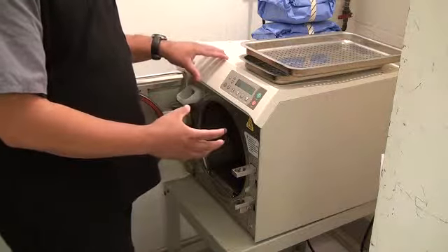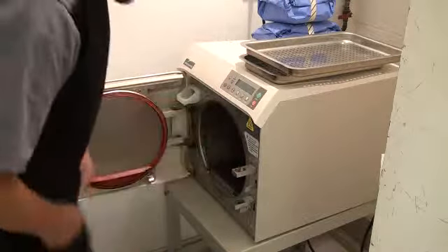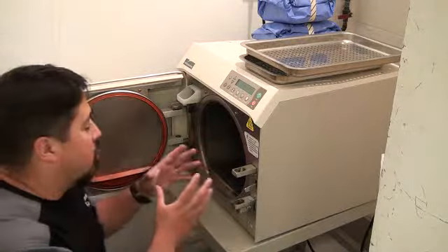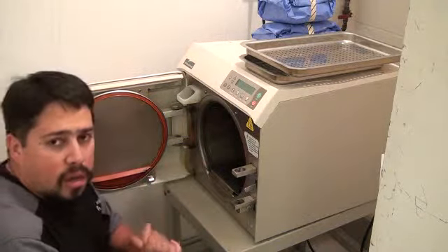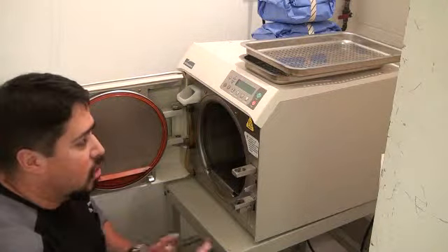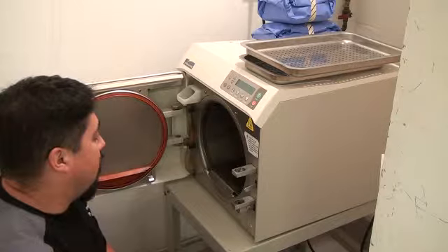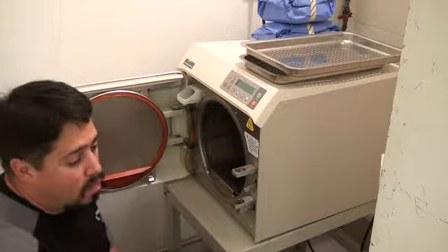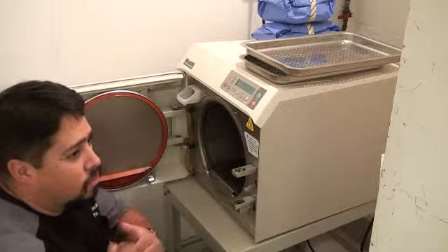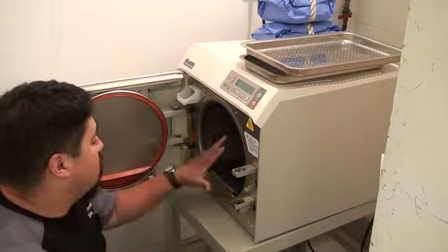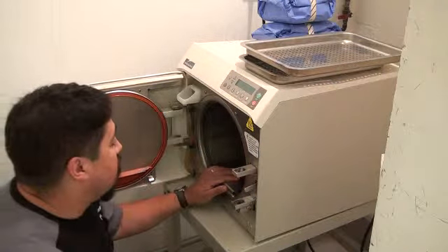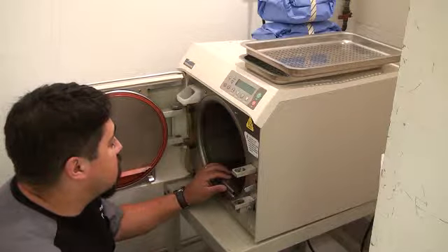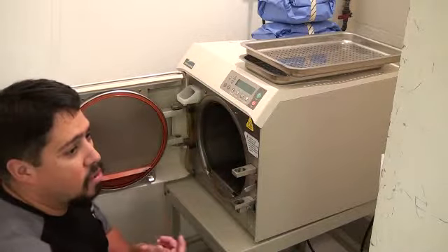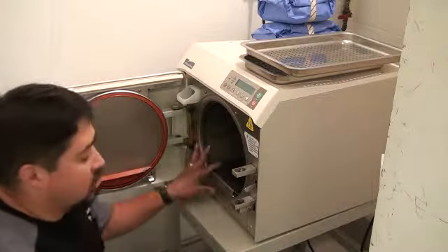And this allows, once the air is gone, the pressure inside the autoclave to build until the temperature and pressure needed to sterilize the packs or the pouches or hand pieces is achieved. You can put stuff in here unwrapped depending on what equipment it is you need, I believe. Once it has gone through its sterilization cycle, the machine cools down and the steam is turned back into water and goes back into the reservoir portion.